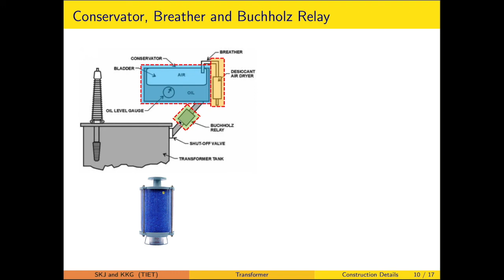However, when the temperature reduces, the oil has to go back to the transformer tank, so the breather sucks in the air. To eliminate the moisture, this breather is fitted with silica gel crystals. The purpose of the silica gel crystal is to remove the moisture from the air. Otherwise, when moisture comes in contact with the transformer oil, it will contaminate it and the deterioration will be much faster. So this moisture has to be eliminated anyhow. And we will also have the Buchholz relay, which is a gas actuated relay.